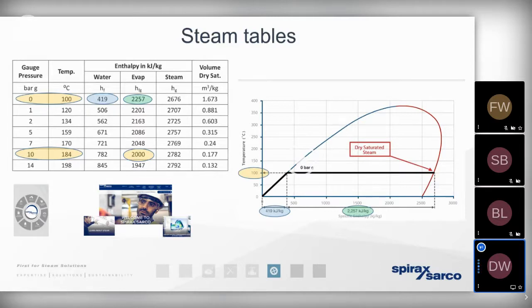But that's all well and good. We don't want boiling water. We want steam. So we've got to put even more energy into that boiling water to make it fully evaporate and produce dry saturated steam. We need to put what's demonstrated in the next column, the enthalpy of evaporation, also known as the latent heat. Only when we've added the energy demonstrated in this column to the previous column are we going to get steam that exists as a gas. In other words, that water's fully evaporated. So the third column, that's the total heat energy present within the steam. In other words, it's the sensible heat together with the latent heat.